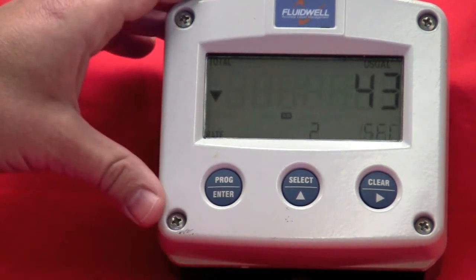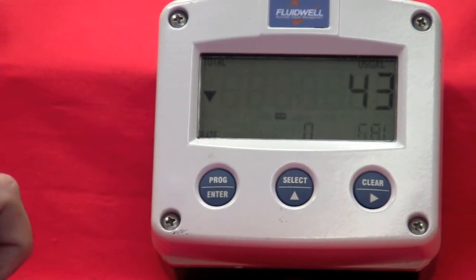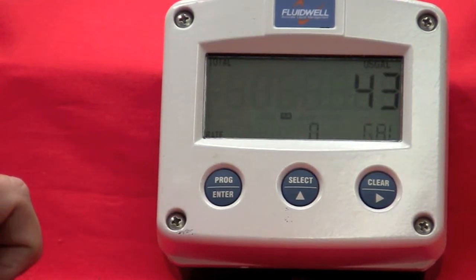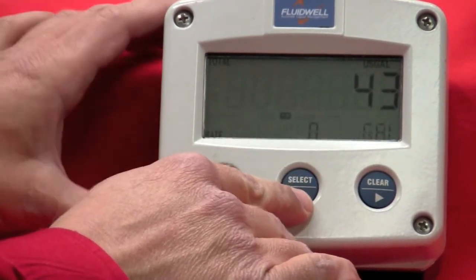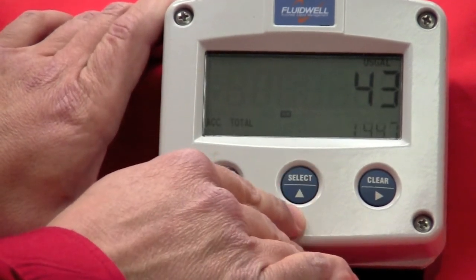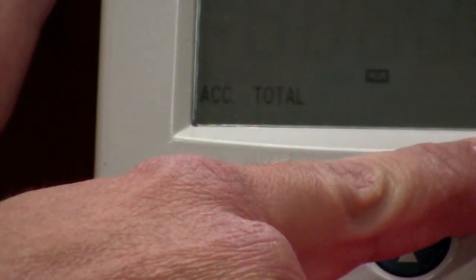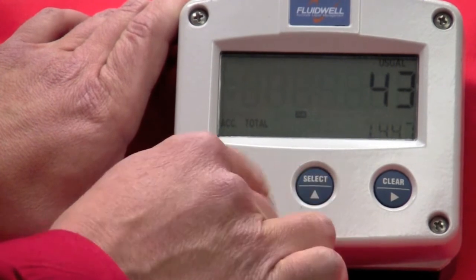This is a NEMA 4X aluminum enclosure for the demo. We have three push buttons here that we can utilize to set up the meter. The most basic function of the meter, you can use the select key, and it's important on how you push these buttons. You want to just push and release. If I push it just once, you'll see the accumulated grand total. This is a non-resettable totalizer.